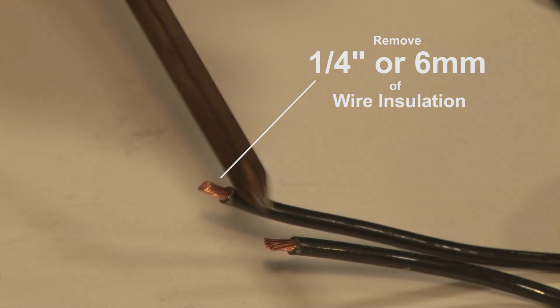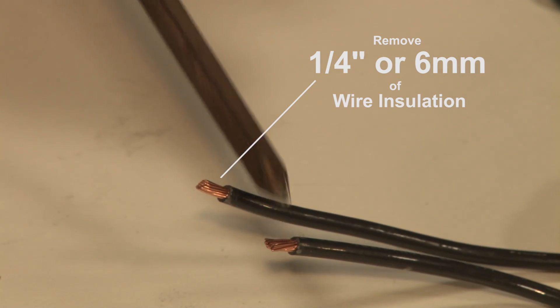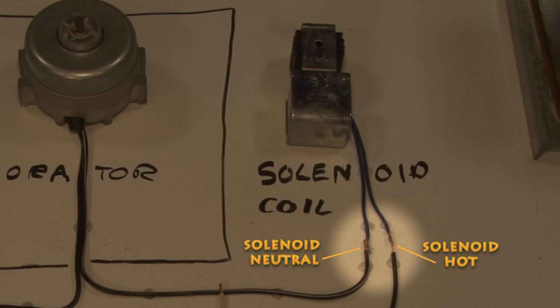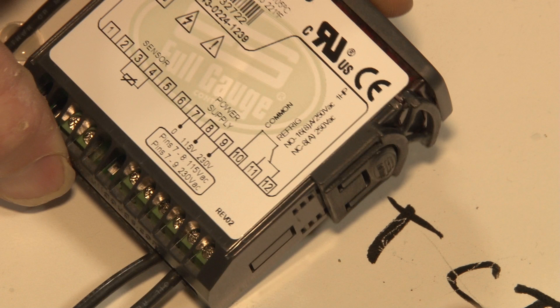And we want to have about a quarter inch or six millimeters of wire exposed to go into the controller. These two wires are left from our thermostat. One of them is our hot coming from 115 volts. The other goes to our solenoid. Here's one more look at those connections.